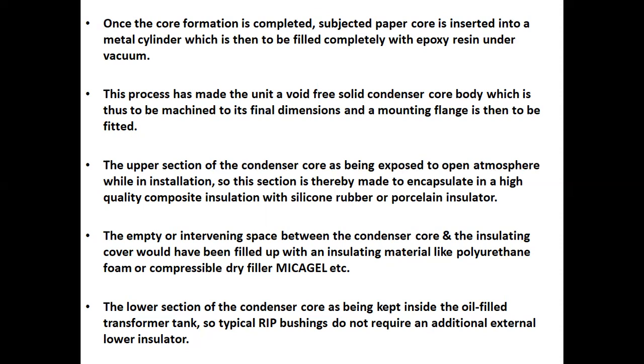The lower section of the condenser core is kept inside the oil filled transformer tank. So, typical RIP bushings do not require an additional external lower insulator.